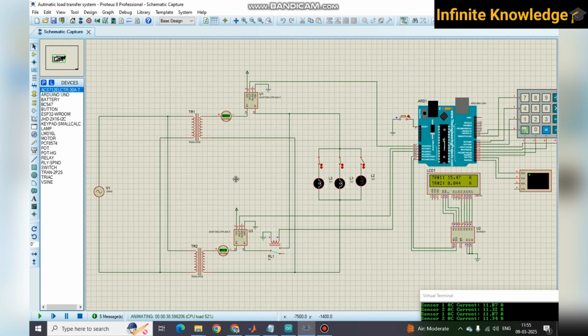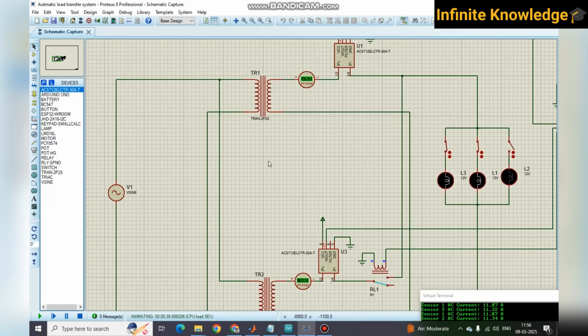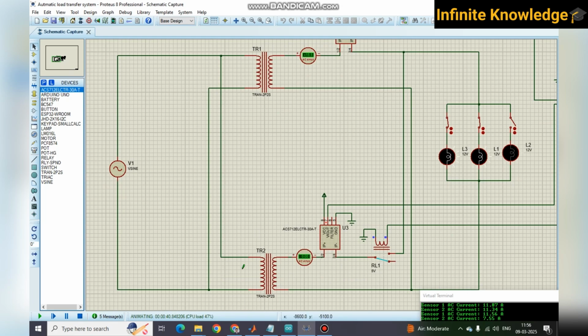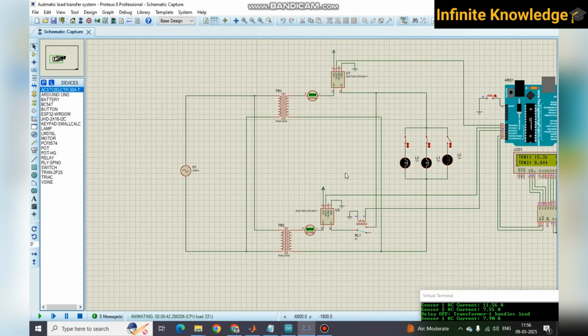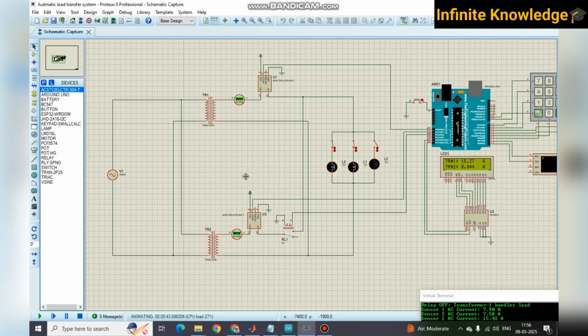Why do we have to do this? Because if the load is lower and at the same time you keep both transformers on, it causes unnecessary losses in the transformer. Each transformer has a particular efficiency, so if both are on and there is a lower load at the secondary side, it causes unnecessary power drop and unnecessary use of electricity. That's why, to save electricity and focus on energy management, we developed this.